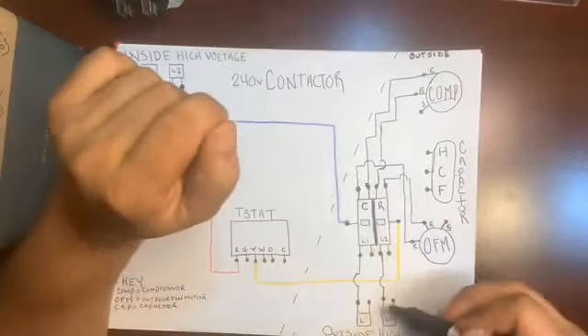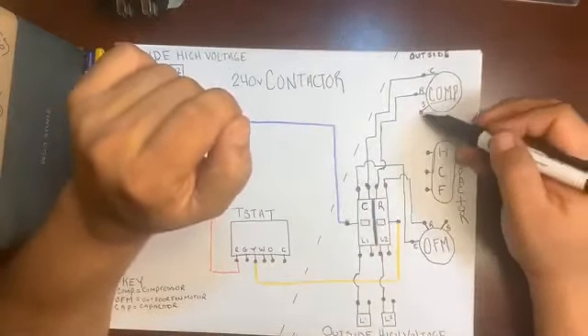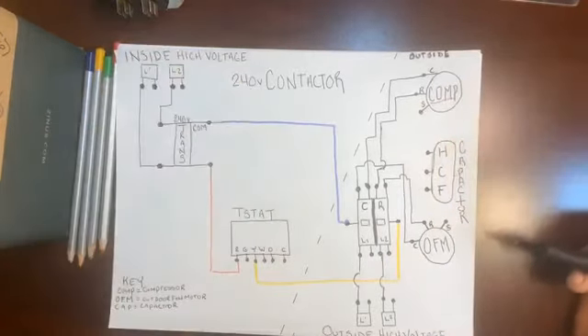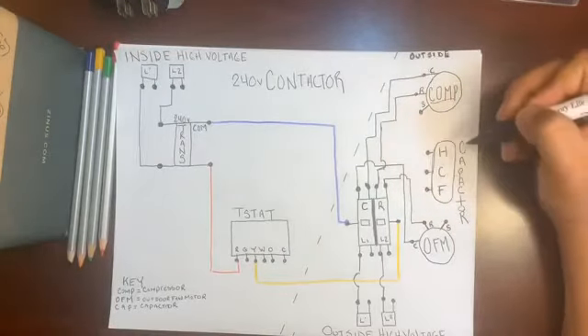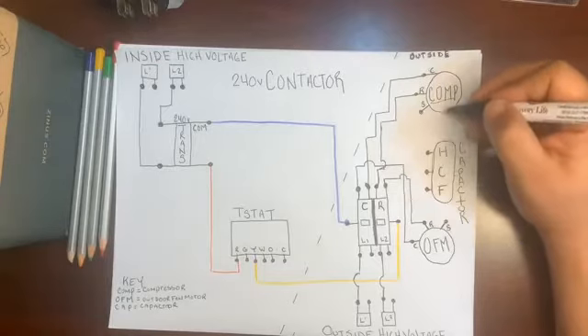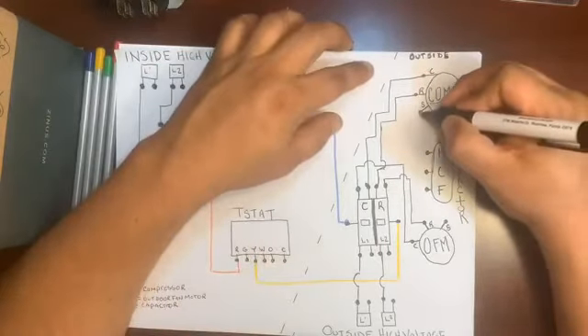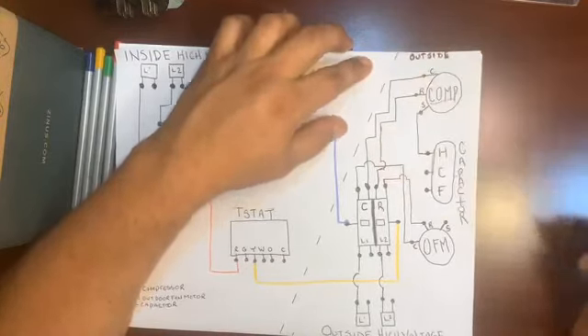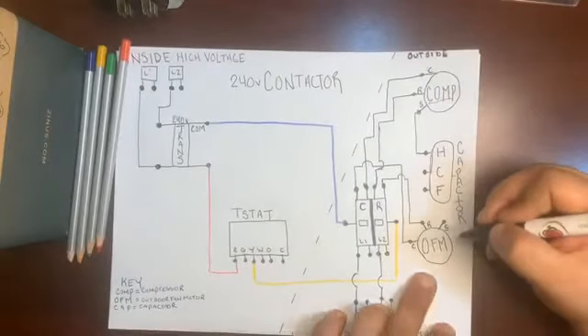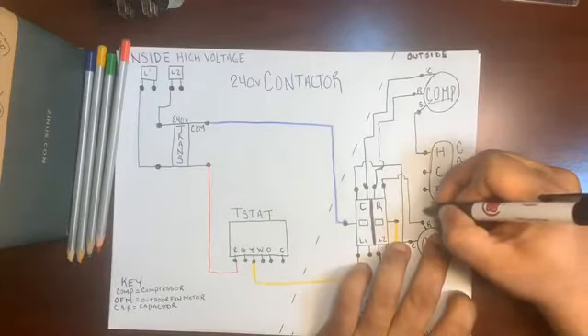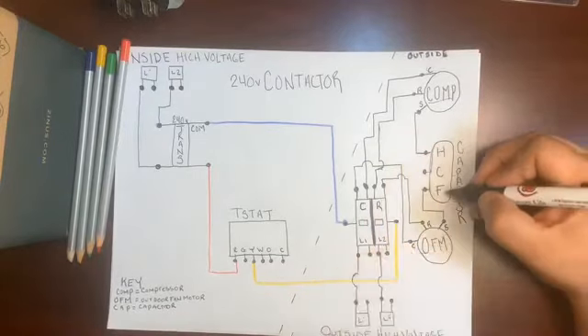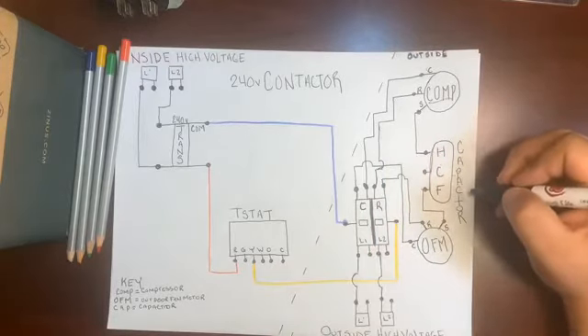So let's see how we turn this capacitor into an artificial leg of energy to almost simulate an L3. We don't have L3. We only have 2 legs of power coming in because it's only 240 volts. But we need to simulate a third leg of energy for the start leg, one on the outdoor fan motor, one on the compressor. The capacitor is how we do it. So we'll start backwards. We'll go from hermetic and fan. Remember that hermetic on the capacitor always feeds the compressor. So we're going to go to the start leg, come on down and hook up to the hermetic. And that leaves us very comfortable here. Here's our outdoor fan motor start leg. I'm going to bring that back and connect right here with the F, the fan portion of the capacitor.